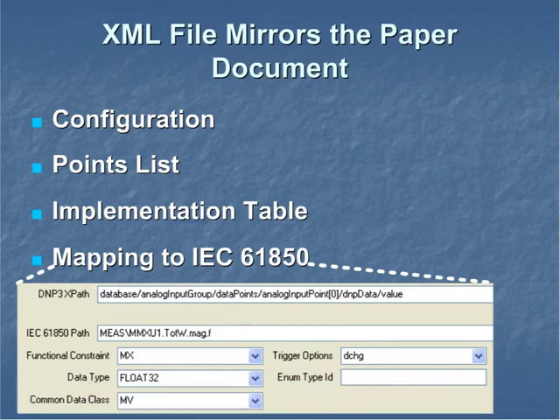An IEC-61850 object model can be represented in the DNP3 XML device profile document by assigning each IEC-61850 data attribute to a configuration parameter, data point, or constant in the DNP3 XML file.